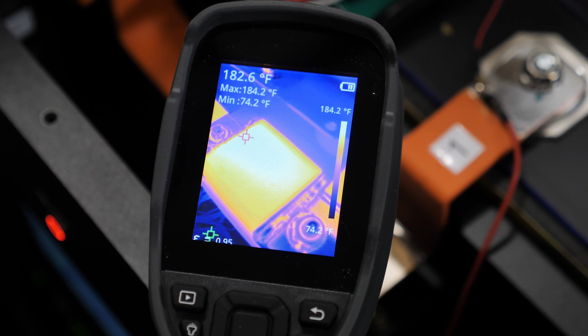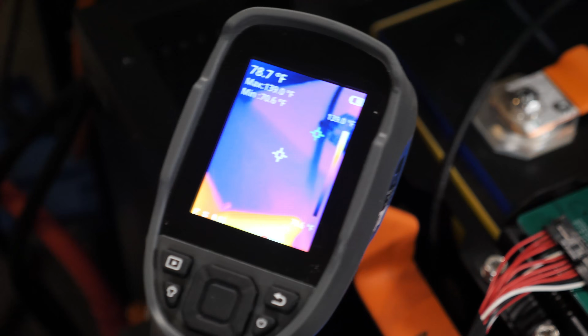Now we're looking at the fuse. We're doing 182, 183 degrees right in the center, and then the bus bar right afterwards is 149, and we'll check the bus bar right here on the top of the circuit breaker.